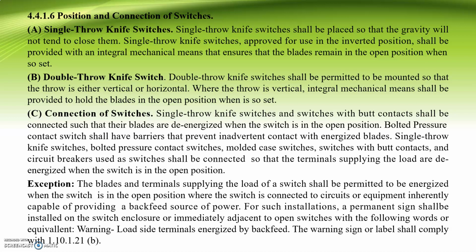Bolted pressure contact switches shall have barriers that prevent inadvertent contact with energized blades. Single throw knife switches, bolted pressure contact switches, molded case switches, switches with butt contacts, and circuit breakers used as switches shall be connected so that the terminals supplying the load are de-energized when the switch is in the open position. Exception: the blades and terminals supplying the load of a switch shall be permitted to be energized when the switch is in the open position where the switch is connected to circuits or equipment inherently capable of providing a back feed source of power.